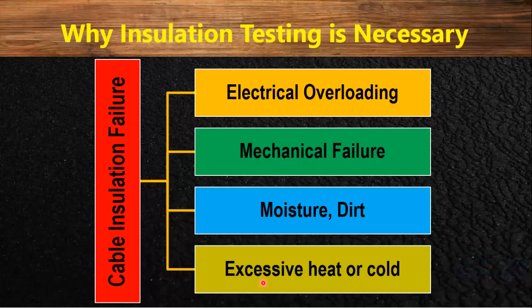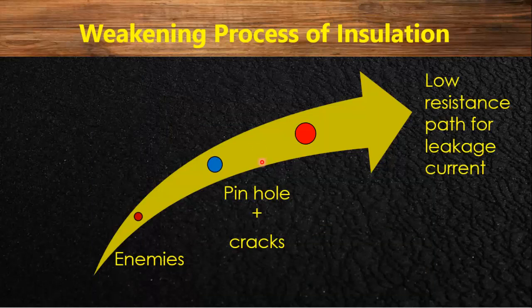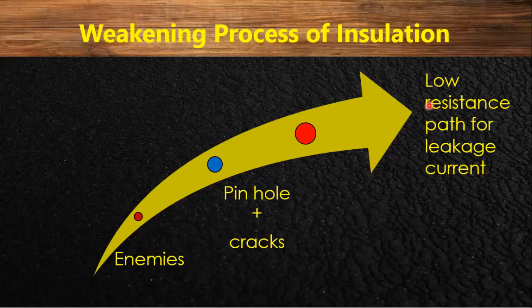Another reason for insulation failure is excessive heat or cold. If the cable is designed for certain operating conditions and we operate it at excessive temperatures — whether heat or cold — it will badly affect the insulation. As these enemies of insulation work over time, combined with electrical stresses, they produce pinholes or cracks in the insulation. In the presence of moisture and foreign matter penetrating the surface, the insulation provides a low-resistance path for leakage current, and once started, these enemies aid each other, permitting excessive current through the insulation and weakening the whole cable and electrical system.